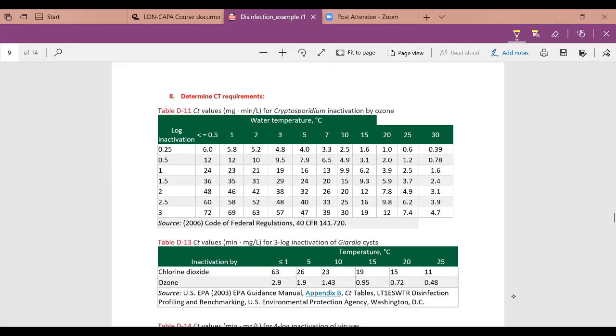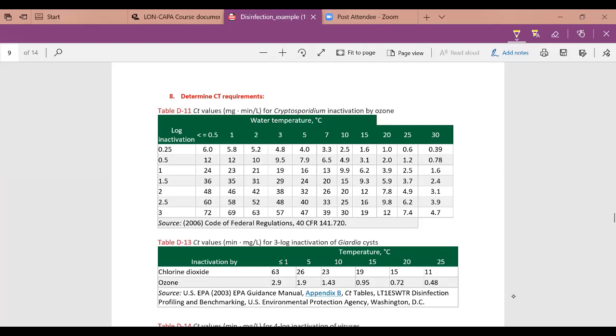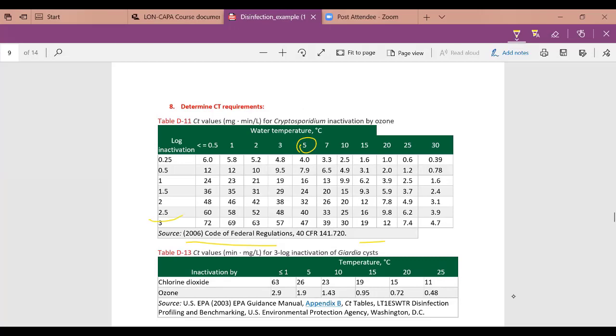Now we determine the CT requirements. EPA provides tables — from Appendix D in your book, actually from the Code of Federal Regulations. At a temperature of 5°C, we needed 2.5 log removal for crypto, so we need a CT of 40 mg/L·min.